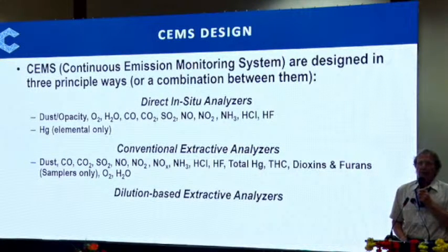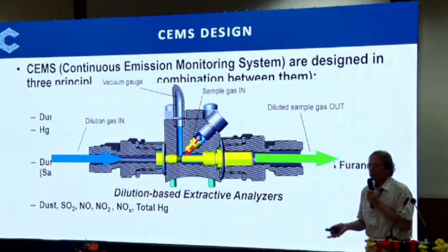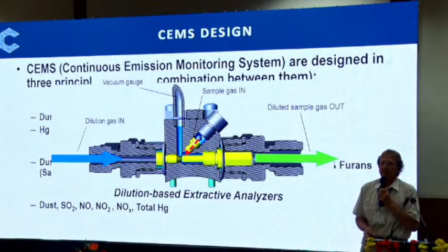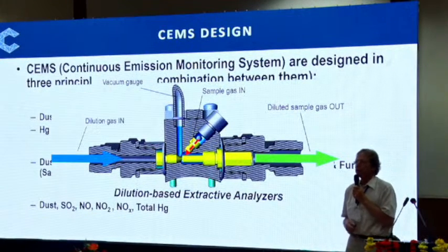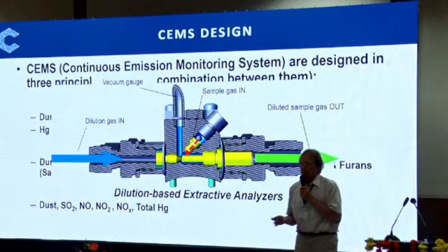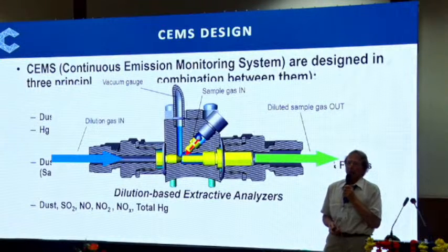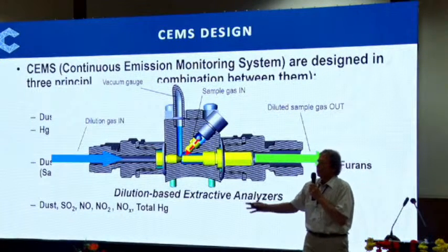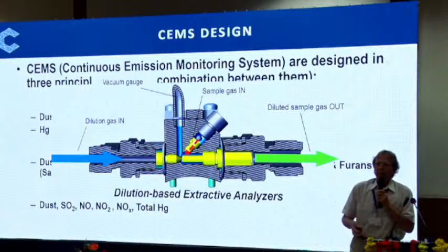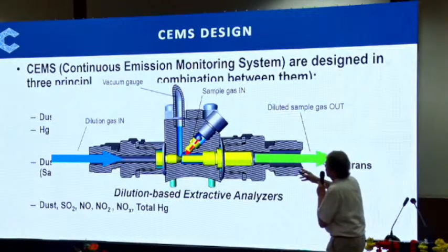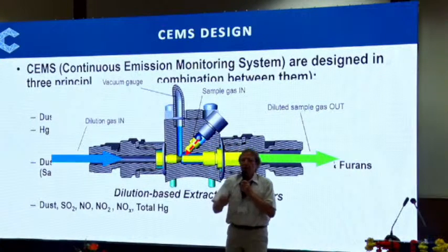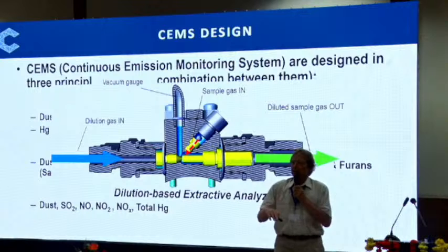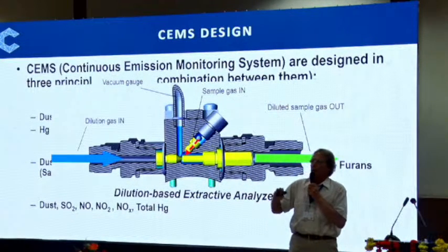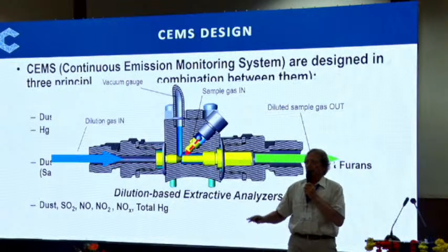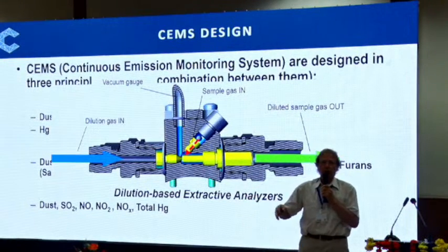The dilution-based extractive analyzers work, yes, for dust as well. The instrument we've seen this morning, plus other extractive instruments, work with an additional dilution. SOx, NOx, total mercury, these are typical dilution-based extractive analyzers where I have a dilution gas. Dilution gas has a dew point of, let's say, 0 centigrade, and I dilute 50 to 100 to 1. Through the critical orifice, when the orifice is critical, I'm getting a constant flow of sample gas, and with the variations of my dilution air, I can vary my dilution factor and stabilize it by controlling my dilution air.